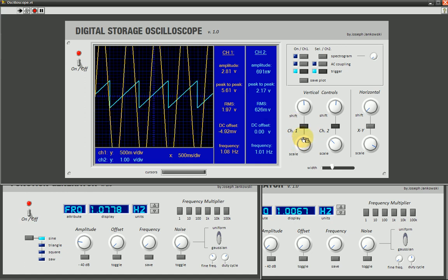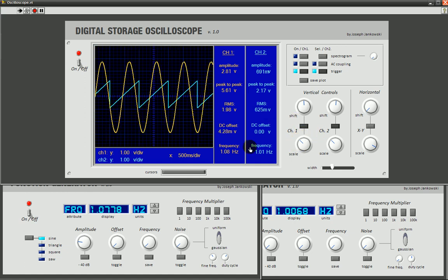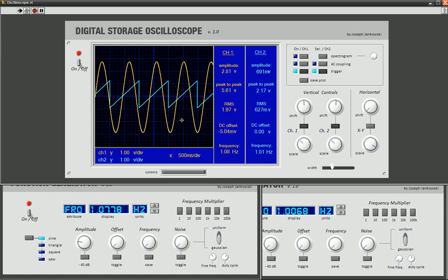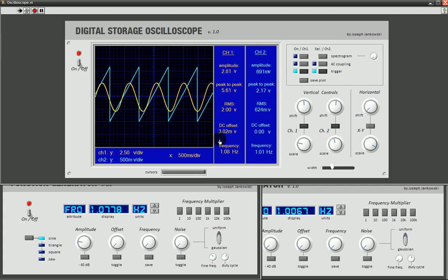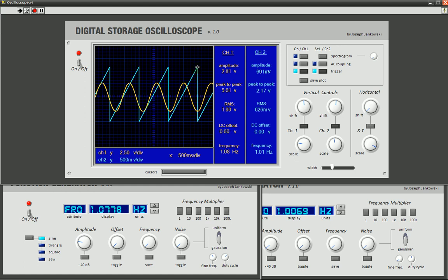You can look here and you can see the volts per division readout for each channel individually. Like for example, right now we have a 5.61 volt peak to peak waveform at 1 volt per division and 1, 2, 3, 4, 5.6. And then on the other channel, it's 1 volt per division. Let's change that to something else just for the heck of it. 500 millivolts per division. And you can see that it's 2.17 volts peak to peak. So that's 1 volt, 2 volts, 2.17.